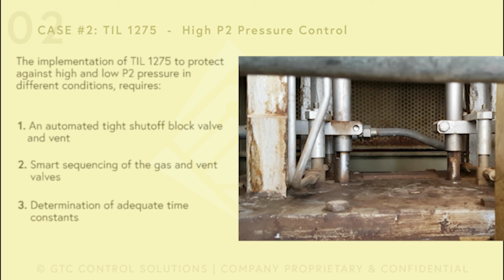How did we come up to that? The first customer we implemented this TIL for, we did the modifications, started the unit, and we had 60 psi P2 pressure, and the speed ratio valve opened 8%. That tripped the unit on the protection. We realized that we had to do something so the valve would not open that much. P2 pressure will be 25 psi, the theoretical value, and the unit would not trip during startup because of the TIL we just installed. That was like chasing our tails.